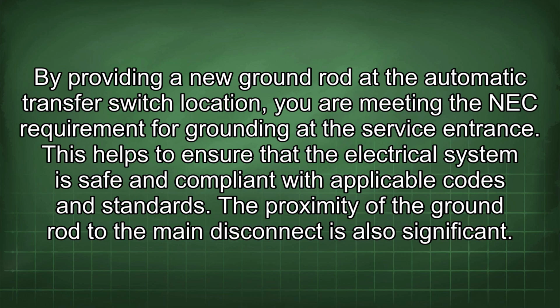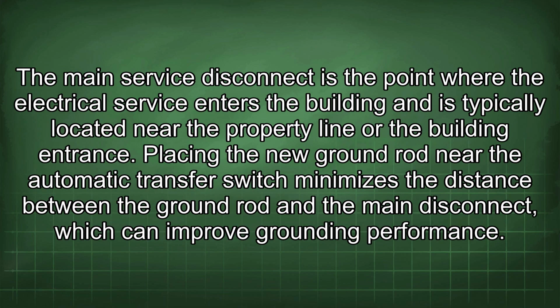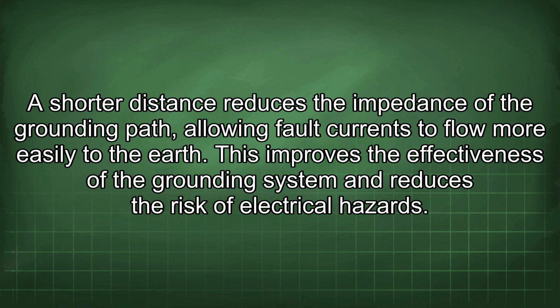The proximity of the ground rod to the main disconnect is also significant. The main service disconnect is the point where the electrical service enters the building and is typically located near the property line or the building entrance. Placing the new ground rod near the automatic transfer switch minimizes the distance between the ground rod and the main disconnect, which can improve grounding performance. A shorter distance reduces the impedance of the grounding path, allowing fault currents to flow more easily to the earth. This improves the effectiveness of the grounding system and reduces the risk of electrical hazards.